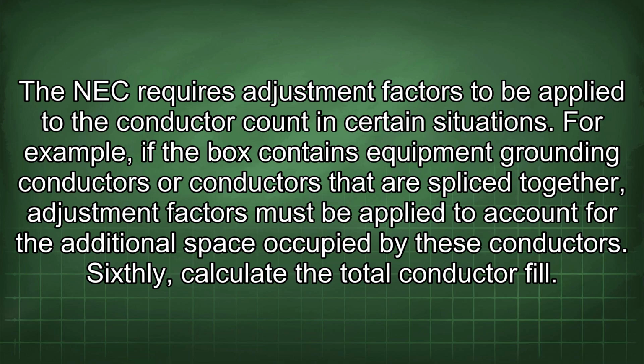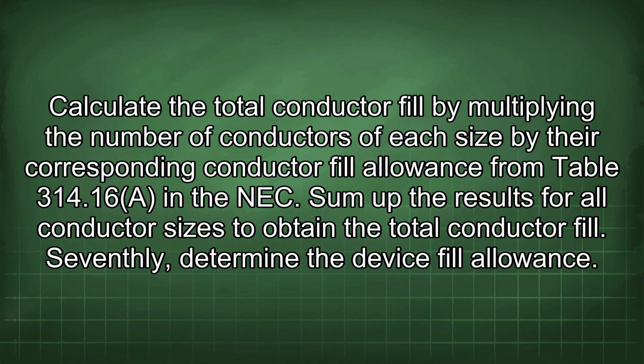Sixthly, calculate the total conductor fill. Calculate the total conductor fill by multiplying the number of conductors of each size by their corresponding conductor fill allowance from Table 314.16 in the NEC. Sum up the results for all conductor sizes to obtain the total conductor fill.